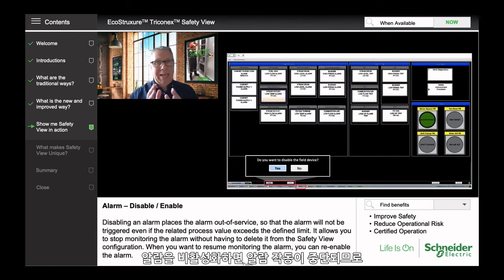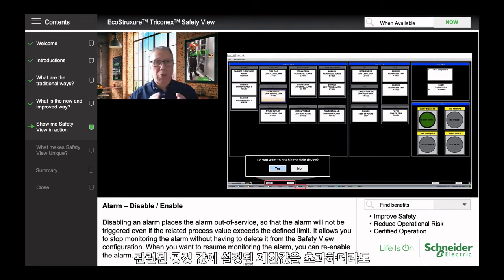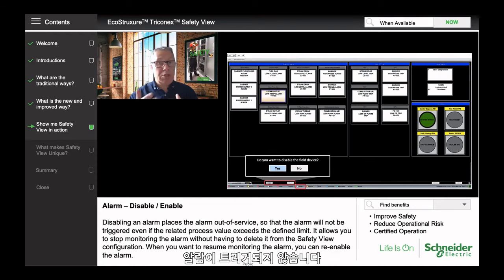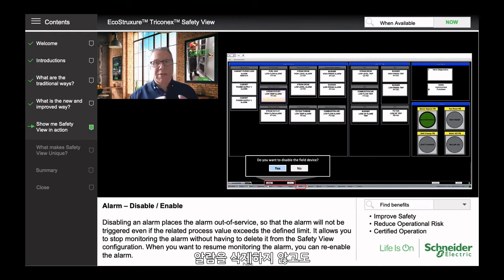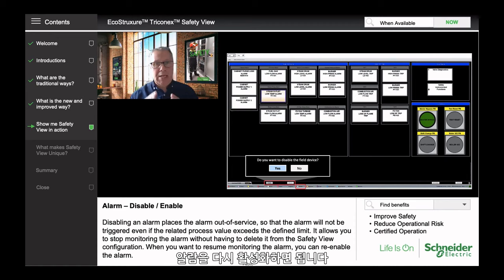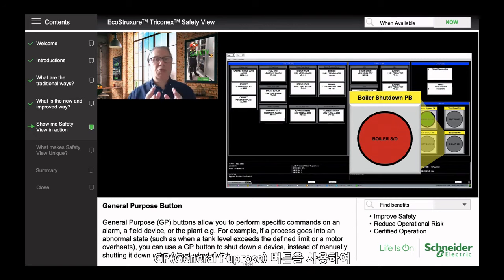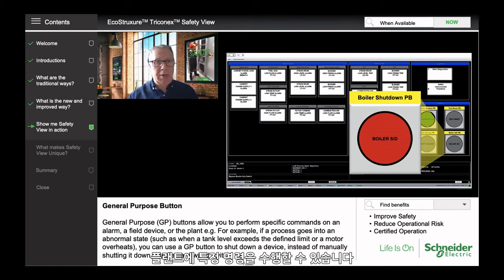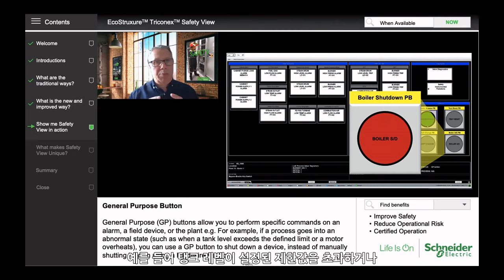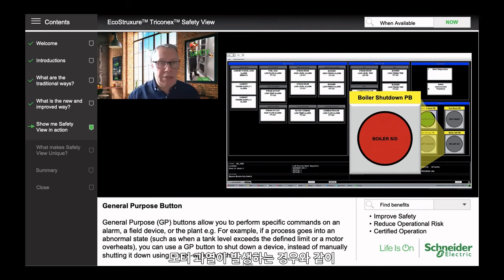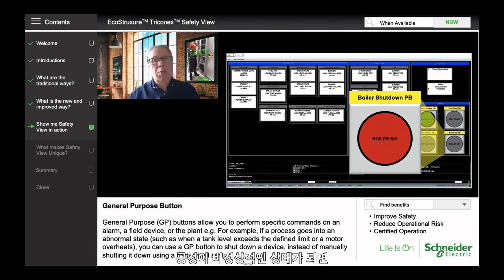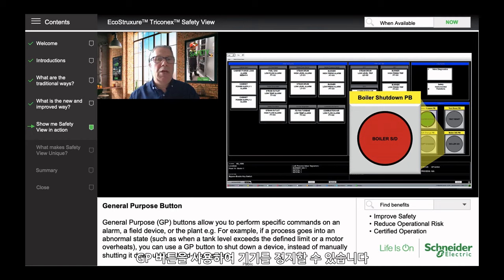Disabling an alarm places that alarm out of service, so it will not be triggered even if the related process value exceeds the defined limit. It allows you to stop monitoring the alarm without deleting it from the configuration, and when you want to resume monitoring, you simply re-enable it. General purpose buttons allow operators to perform specific commands on an alarm, a field device, or even on plant conditions. For example, if a process goes into an abnormal state — such as a tank level exceeding the defined limit or a motor overheating — the operator can use the GP button to shut down that device instead of manually using a hardwired switch.